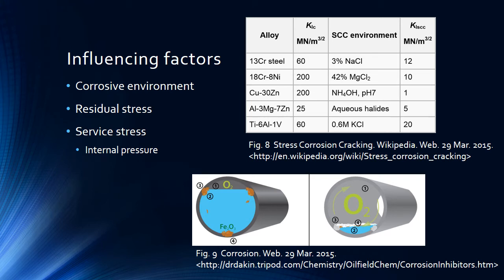There are a few factors which influence environmentally assisted cracking in fire sprinkler pipelines. First is the corrosive environment. Every specific material has a relative corrosive environment in which environmentally assisted cracking, or more specifically stress corrosion cracking, will occur.